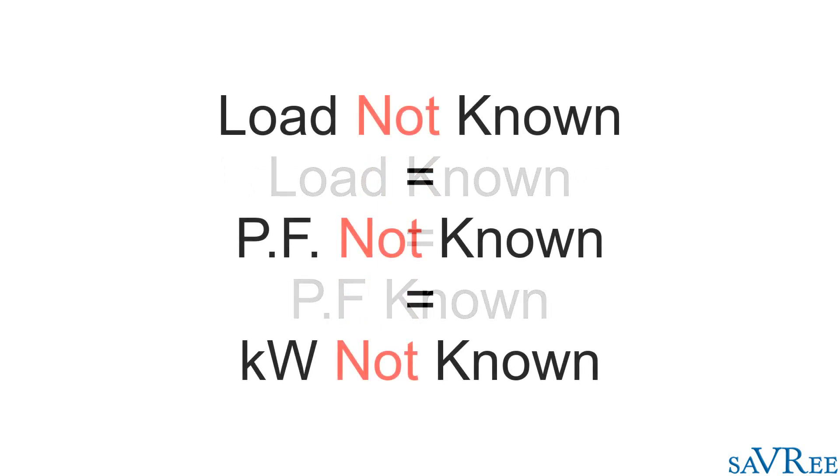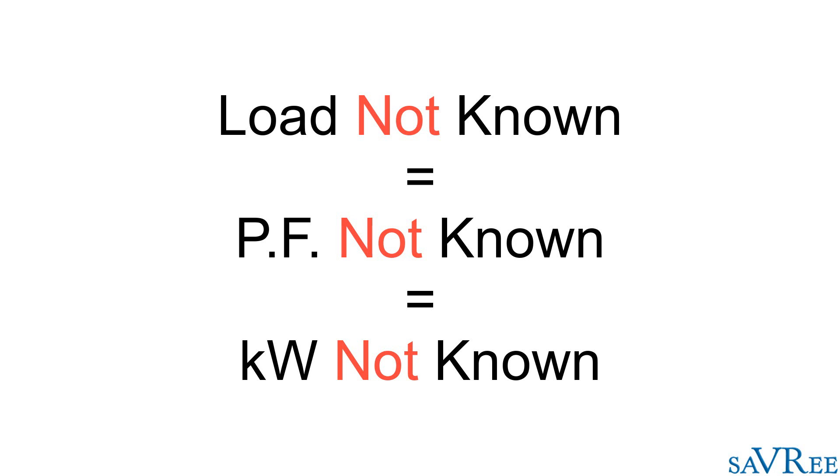If the power factor is known, a rating could be given in watts. But the power factor is not known because the load is not known. Therefore, it's not possible to give the transformer or generator a rating in watts. It's for this reason that transformers and generators are rated in voltage ampere.